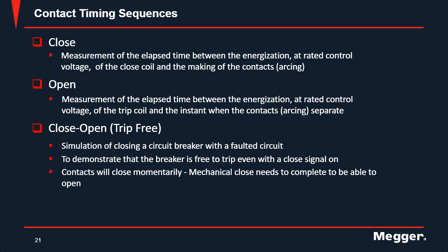And then you have your close open, which is also known as a trip free. It just simulates the breaker closing in on a fault to demonstrate that the breaker is free to trip whenever the close signal is still on. So basically the contacts will close momentarily. The mechanical close needs to be completed to be able to open.